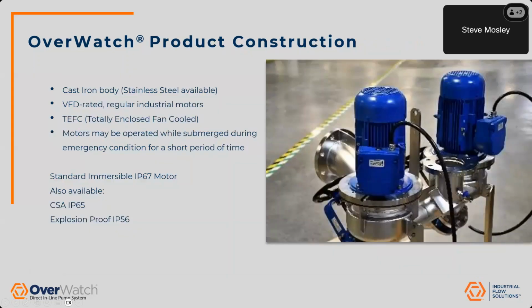The motors on these systems have a cast iron body. If for some reason you are in a corrosive environment where you did need stainless steel motors, we do have the option to source those. The overall body of the system is 304 stainless steel. And again, if you do run into a more corrosive application, we've got a 316L stainless steel body available as an option.